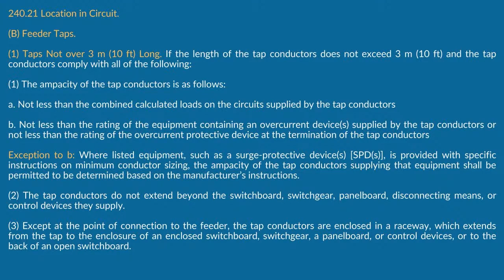I'm going to give everybody a rule of thumb here when you're looking at sizing taps. This is very simple: if you take any tap that's 10 foot or less, you divide by 10. Now, every other tap, guess what you take it at? A third. Anything longer than that, you take it at a third.